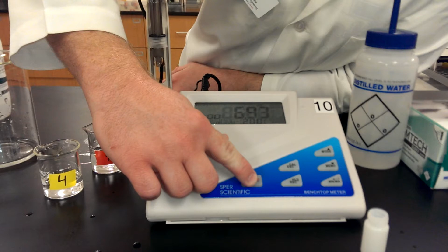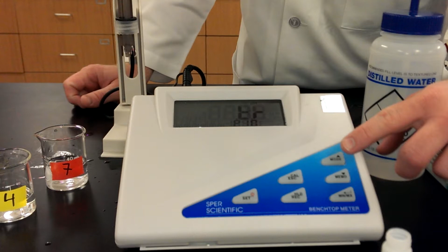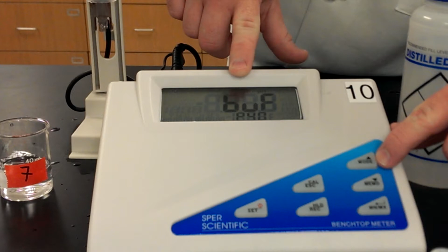First thing we're going to do is push the set button for just a few seconds. Again, we're going to hold it down. Okay, and this is going to go to a mode where we can change the settings. So we're going to use either the up or the down arrow, and we're going to find the mode that says BUF. So I just pushed the up arrow 3 times, and it says BUF. That's the buffer. That's how we check and make sure our buffers are set correctly. After you've done that, you're going to push the enter button.